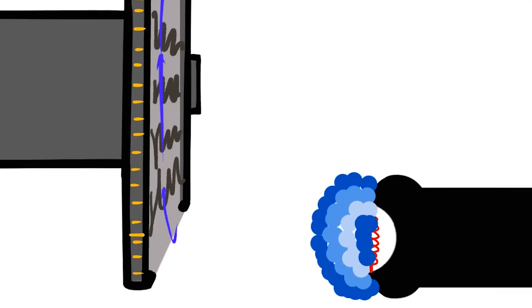As you push it halfway down, that delay is because the anode starts to begin to rotate. The anode needs to rotate to a constant velocity — really fast. The x-ray production produces a lot of heat, so if the anode isn't rotating at a constant speed, more heat will be applied in some locations than others as it's turning. So there's a delay because it has to get to a constant speed before it will allow you to take the exposure.